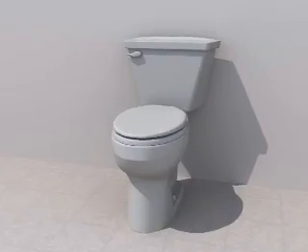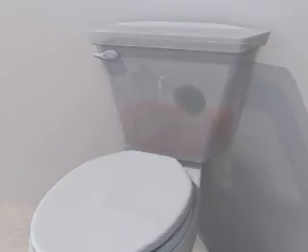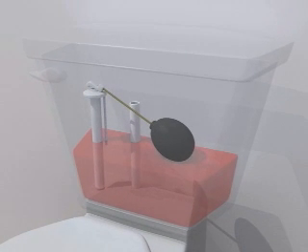As you can see from this diagram, the potable water enters the toilet tank, and if backflow were to happen, the non-potable tank water could flow back into the potable water through the cross connection. However, modern technology has given us new tools to prevent backflow in our water system. They are called backflow prevention devices and assemblies. There are two basic types: reduced pressure or a double check valve.